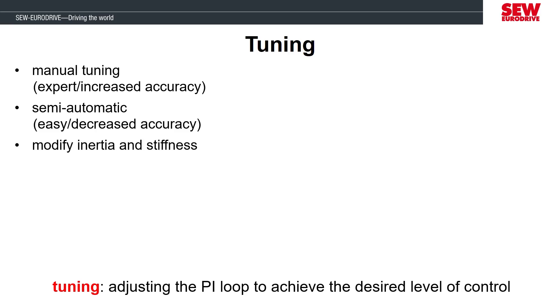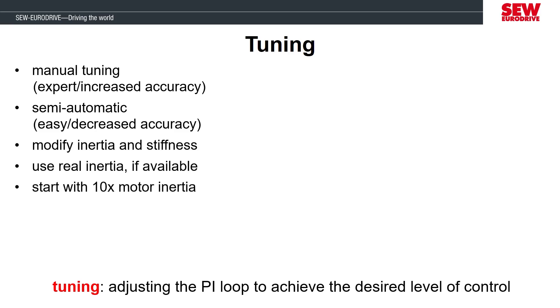The semi-automatic tuning method is done by modifying the stiffness and inertia values only and then applying the recommended tuning parameters from the MOVIDRIVE startup. If you know the real inertia of the system from the machine designer, then you can use that value for the inertia. If you don't know the real inertia, that's okay. In those scenarios, we recommend starting with an inertia value that is 10 times the motor inertia. If you're using an SEW motor, it will have the motor inertia shown in the startup tool, so finding that value is very easy. Setting the load inertia to 10 times the motor inertia is just a starting point and it will likely change as you go through the process of improving the performance.